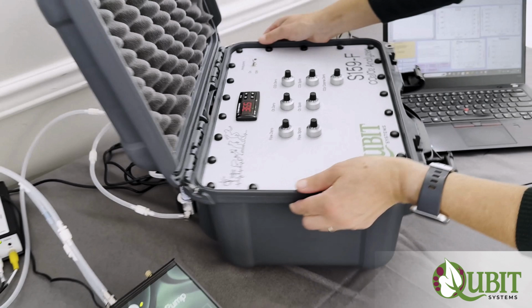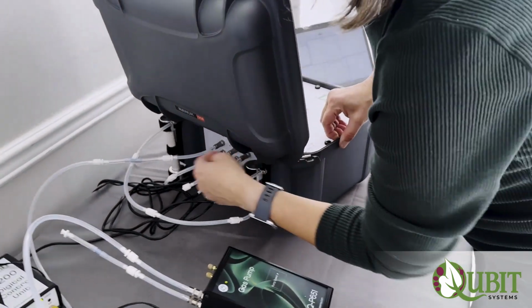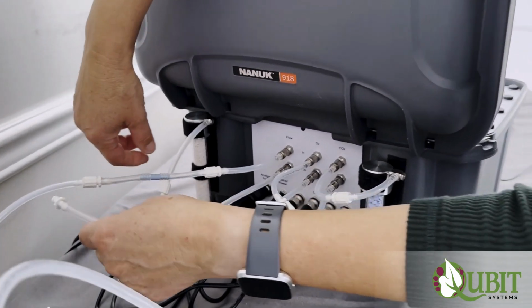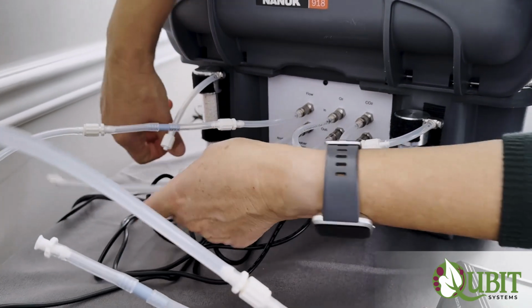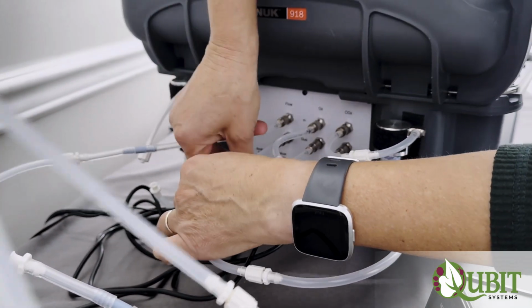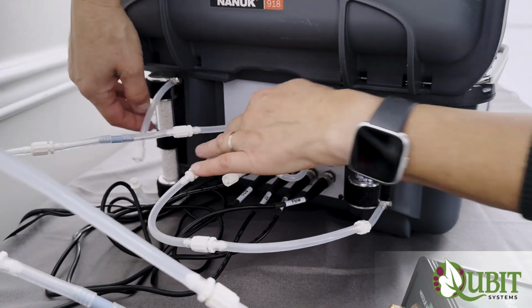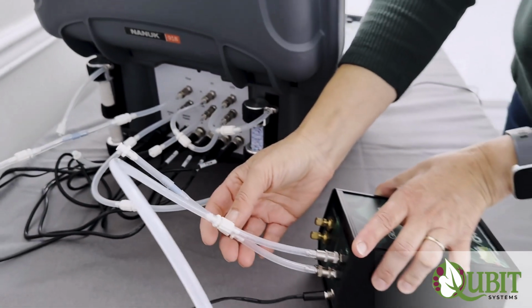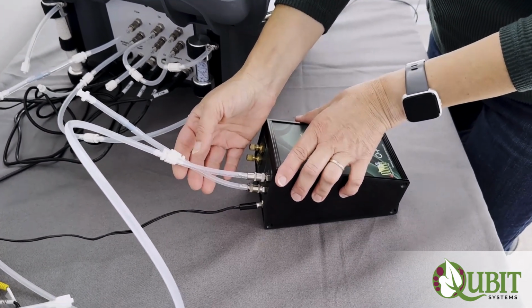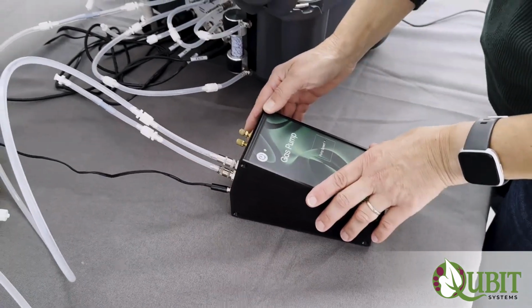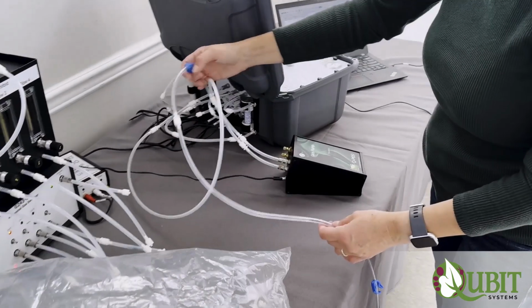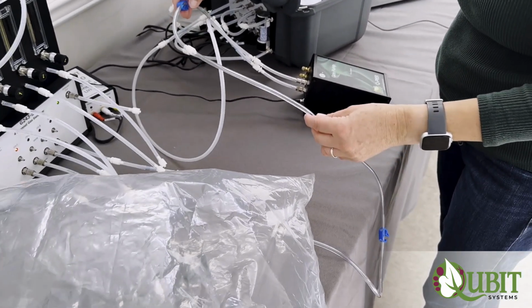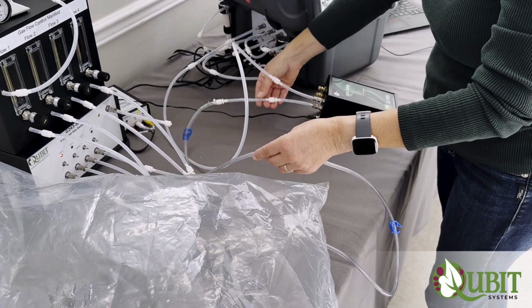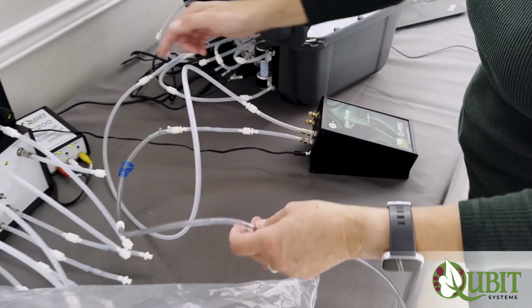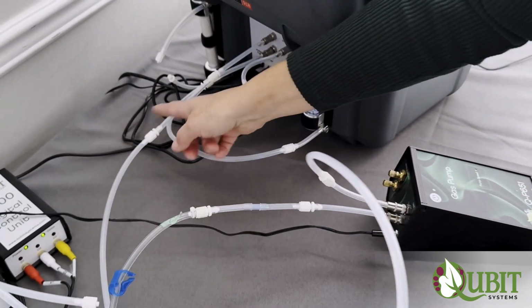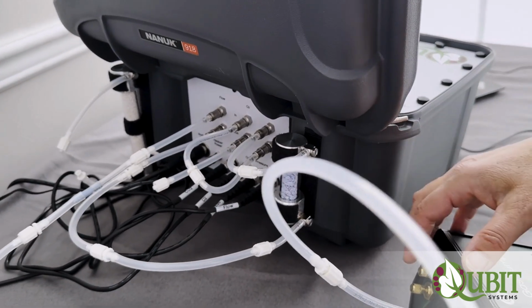Now for our second point, we will remove the soda lime, so the CO2 is not being scrubbed anymore. Remove the soda lime and just connect the drying column directly to the flow monitor. And now we need to connect a gas bag with a known CO2 standard gas to the pump. So here we have a gas bag with a 505 parts per million levels of CO2. We're connecting that to the pump input, and that's what's being delivered from the pump to the flow monitor and the rest of the system.